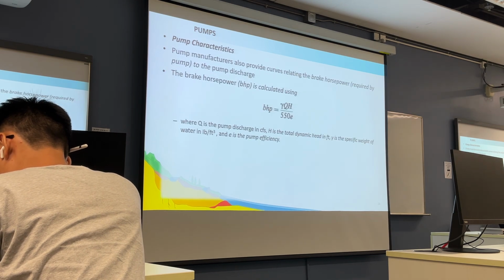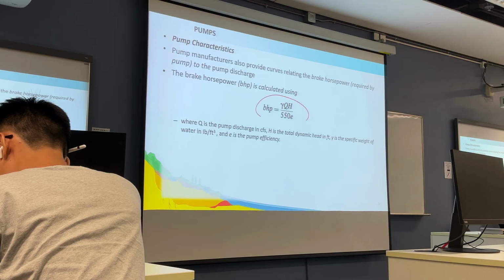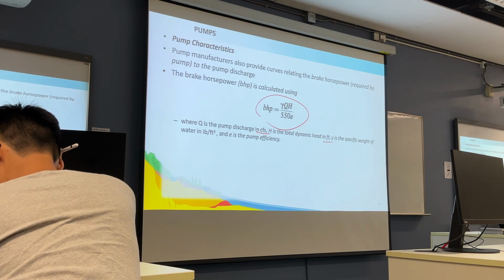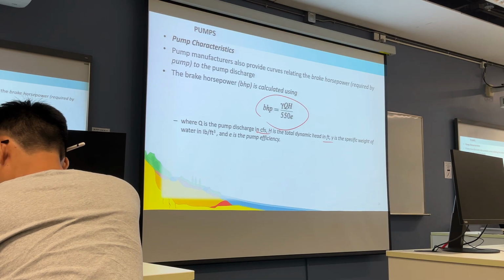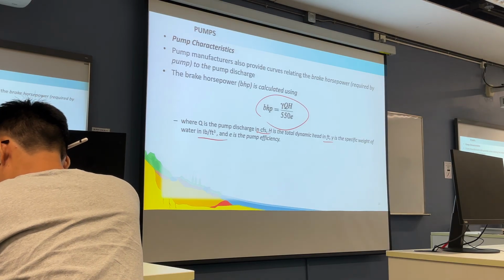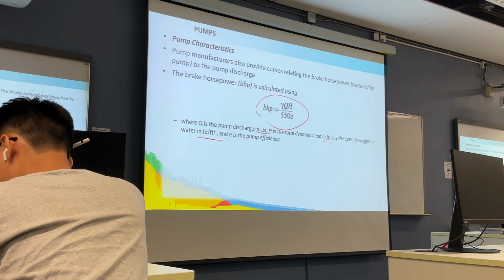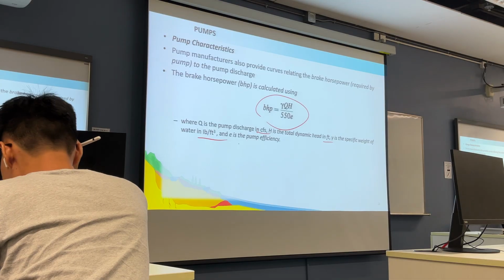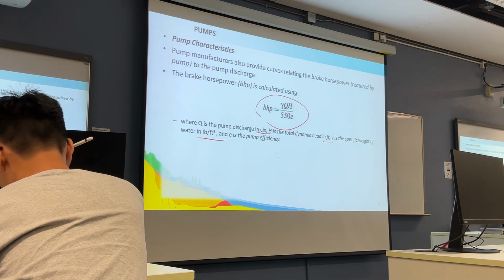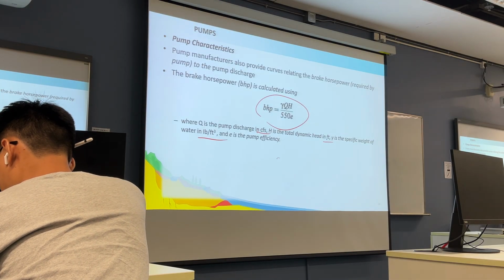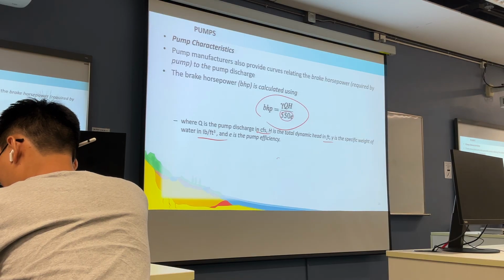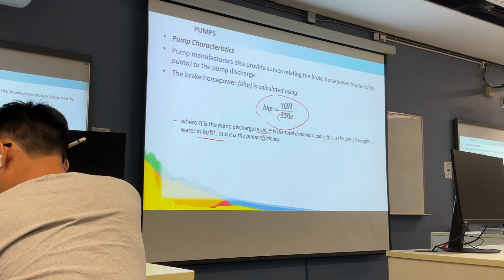Here we are talking about the pump power calculation. This equation is for U.S. customary units: discharge in CFS, pump head in feet, and specific weight of water in pounds per cubic foot. E is the efficiency, with no unit. So the equation has a coefficient of 550.